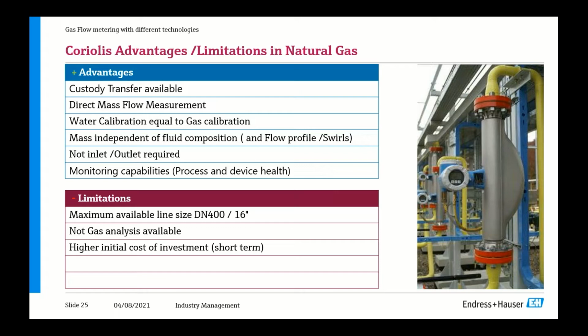Here we mention the limitations and, of course, the advantages of Coriolis meters. One of the main points is that custody transfer is available. So for custody transfer applications, we have the right Coriolis meter. You have direct mass flow measurement. Water calibration equal to gas calibration is a big plus. I suggest that everybody think about it because we have had issues with many customers who didn't select the right device for their application, and they went through a very costly way of calibrating or verifying their meters. It's independent of fluid composition, so also no issues with flow profile or swirl, and no inlet and outlet are required. And since Coriolis measures the flow mass of the fluids, its accuracy is independent of fluid composition, like I mentioned before, right?